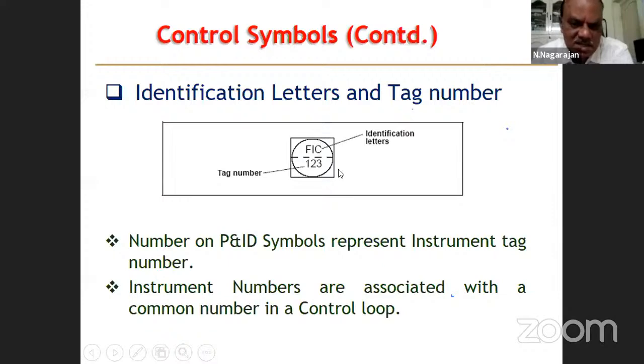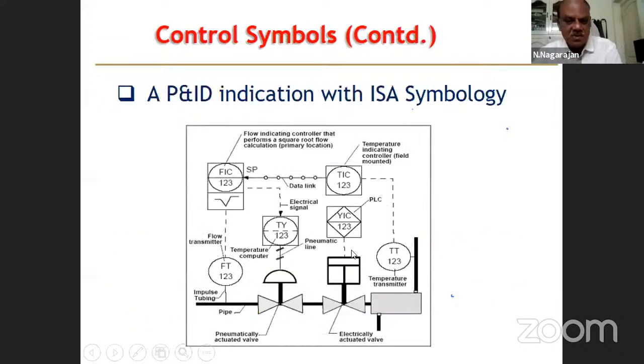This is a DCS symbol. Okay. Dotted line shows some inaccessible thing. This is the tag number FIC 123. So the number on P&ID symbols represents the instrument tag number. If it is the whole loop, flow indicating controller loop, the flow sensor will be FT123, controller is FIC123. Then the controller output to the valve will be FV123. Okay. Next diagram, we will see all those things.